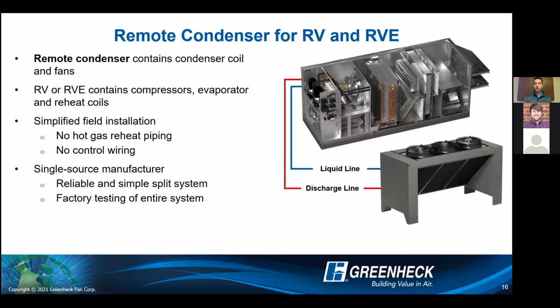Remote condenser related to the cooling components that we have with the RV/RVE. This split system is a little bit different. So if you ever have to deal with split system, obviously balancing a condensing unit by a different manufacturer is pretty tough through the software as well as in the field. So what we do with our remote condenser design is we actually keep the compressors inside the unit itself, giving us the ability to pipe that compressor to the reheat coil. And then that is a nice balanced system, all from factory.